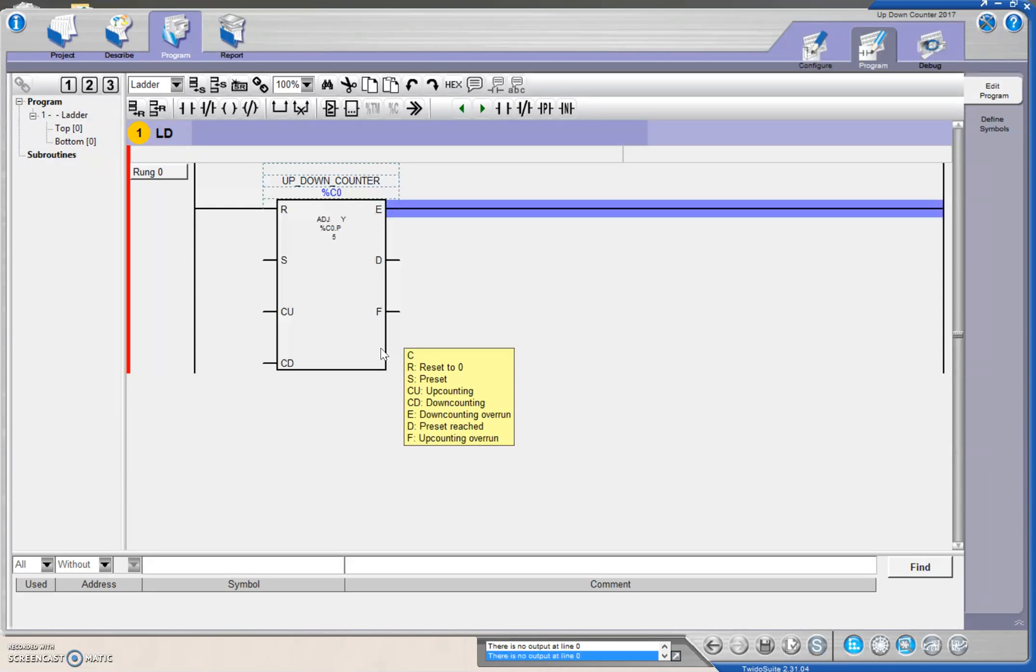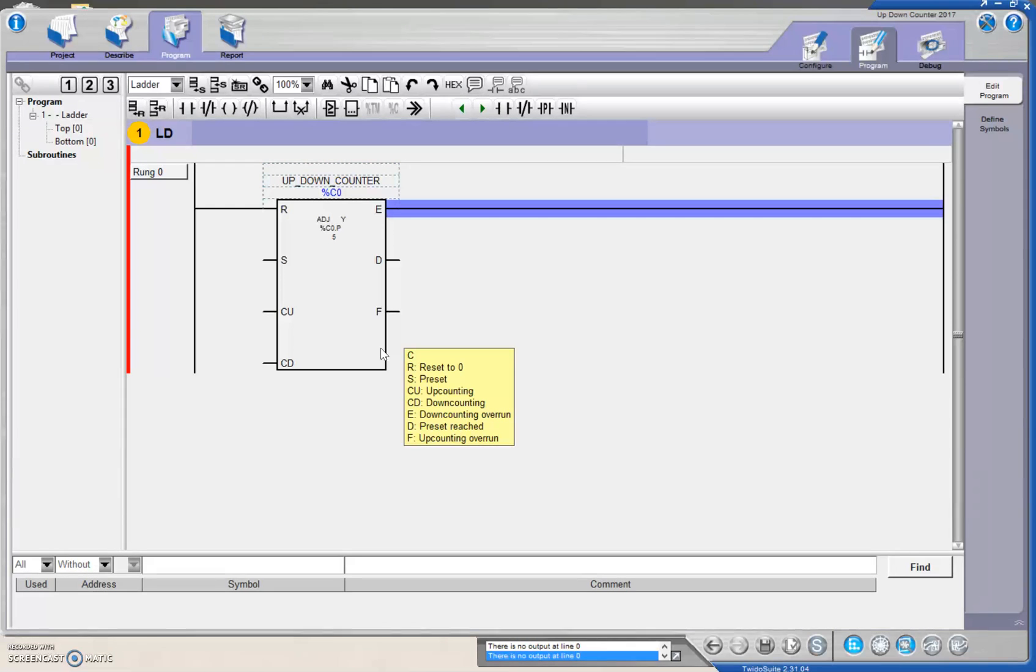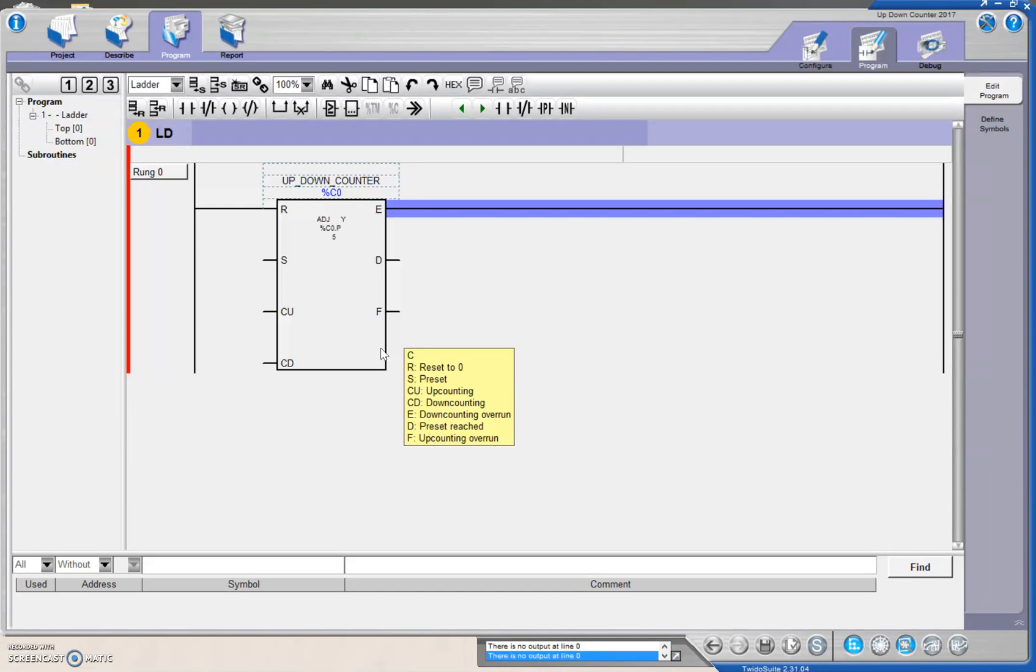So, R is the reset to zero, so that's your accumulated being reset back to zero. S is a preset value that you can input. CU is up count, CD is down count, E is an overrun if you're down counting.